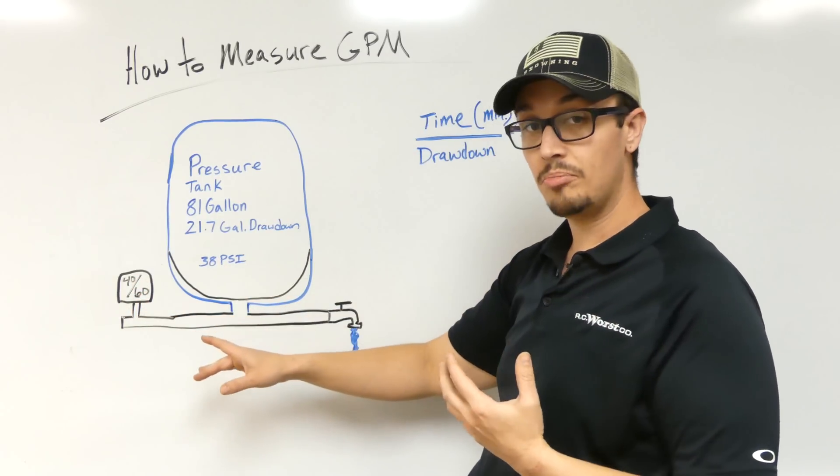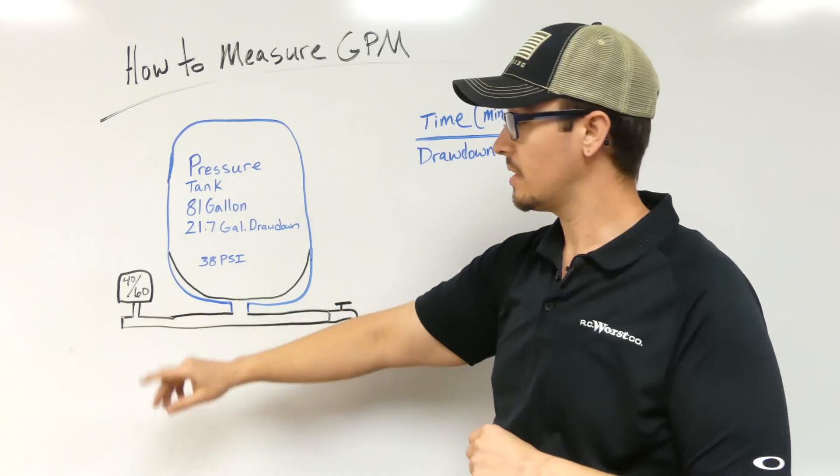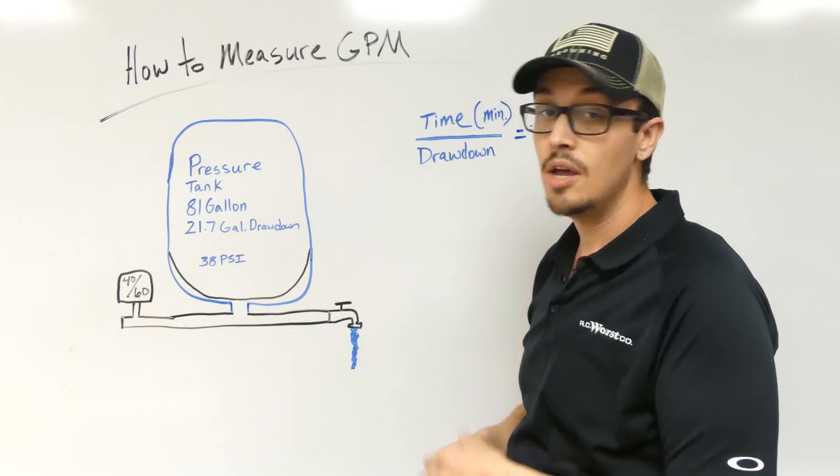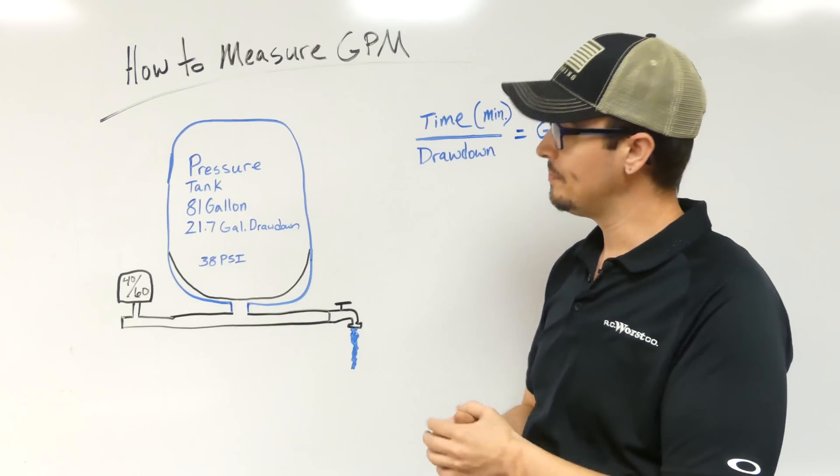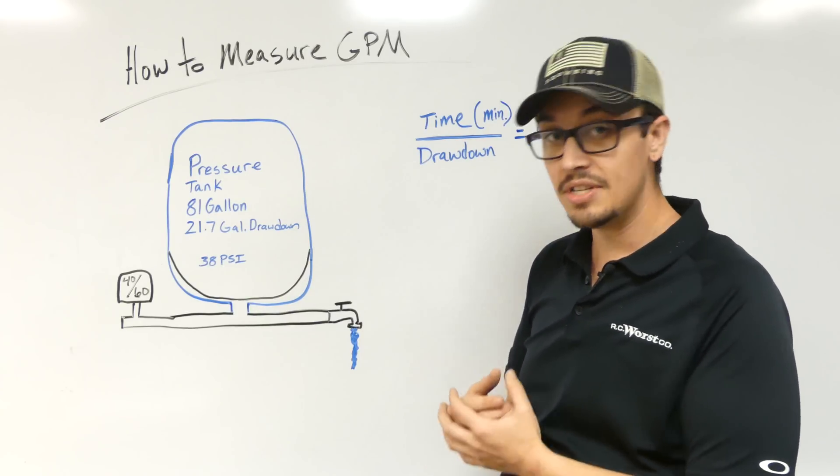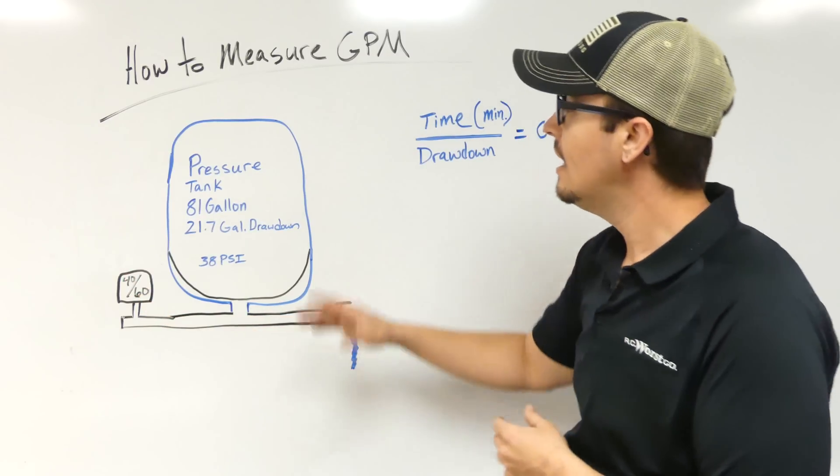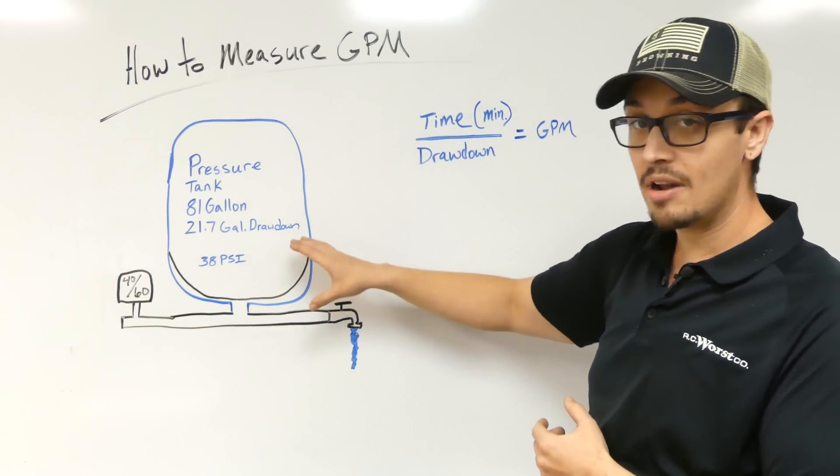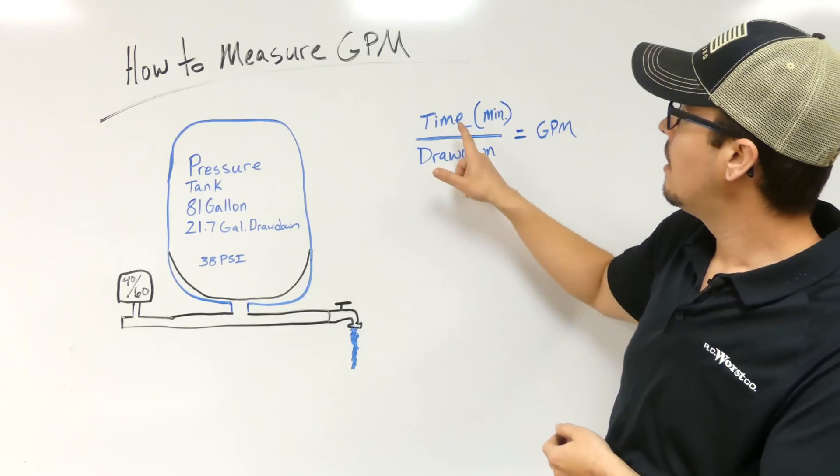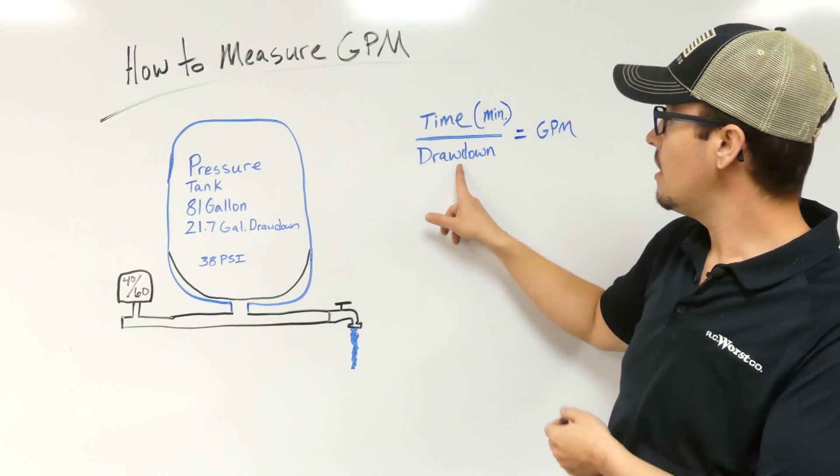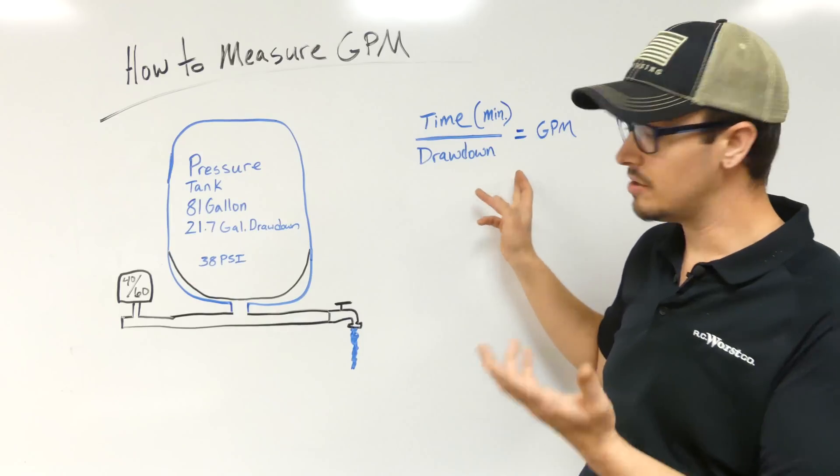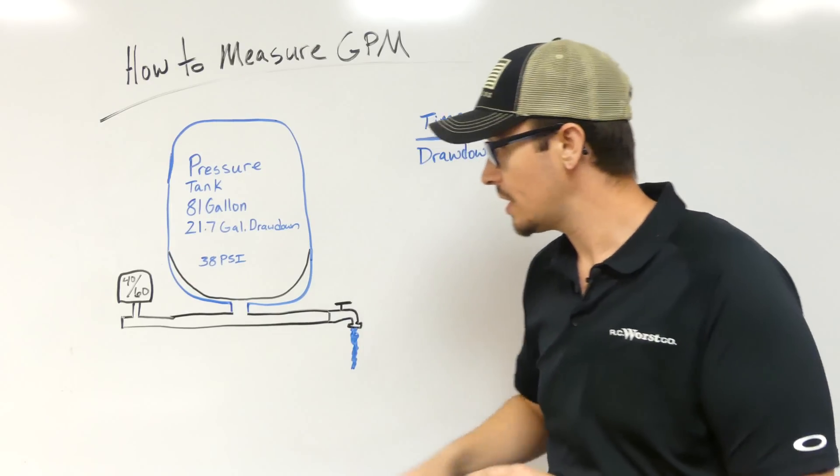Basically what we're going to do is drain everything down till the pressure switch kicks on. As soon as we hear the pressure switch kick on, we're going to start that stopwatch. We're going to measure how long it takes until that pressure switch opens again or turns off. When we get our time over our drawdown, that gives us our GPM.